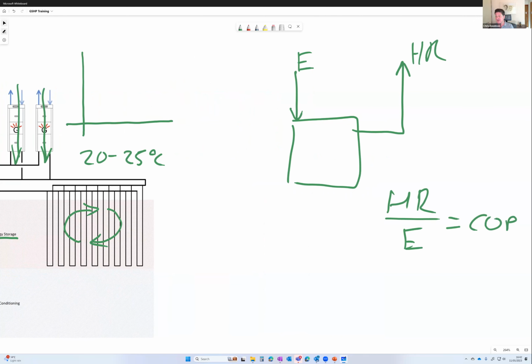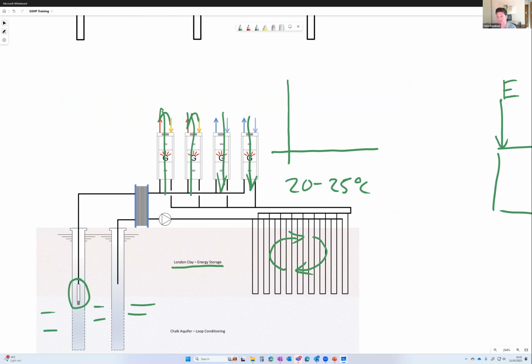I'll come back to the difference between seasonal COP and COP in a minute. Back to my graph, for the specific heat pumps involved, if you draw a graph of their heating and cooling efficiency, they cross over around that 20 to 25 degrees C point.